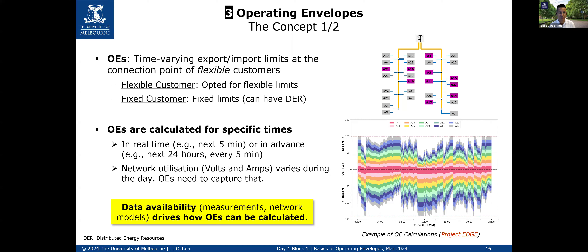Why calculate in advance? Because if aggregators are playing the market, they benefit from understanding what the limits will be in the next few hours so they can plan the use of their assets accordingly. The calculation captures the utilization of assets in terms of voltages and ampacity throughout the day. Data availability drives how this can be calculated — the more data and electrical models you have, the better. On the right-hand side, a graph shows how operating envelopes look for exports and imports, with customers having similar values at a given time step — what we call equal allocation.